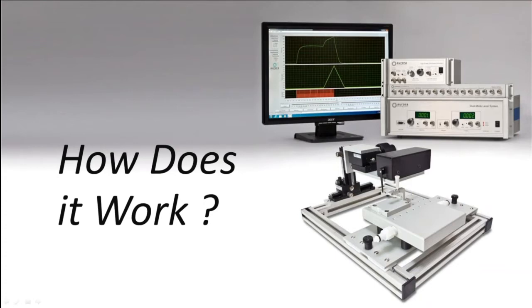So we said that dual mode means it's a combo instrument. It's a force transducer and a position transducer as well. But in addition to measuring force and position, it can also control either one of these parameters while simultaneously measuring the other, and it's able to flip back and forth instantaneously between which parameter you're controlling and which you're measuring.